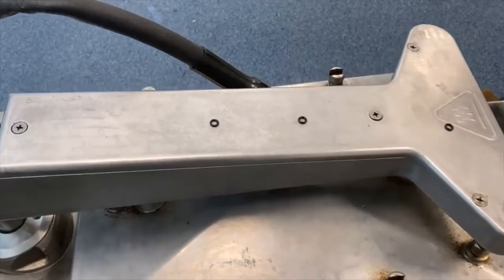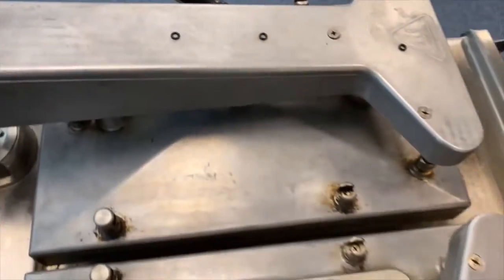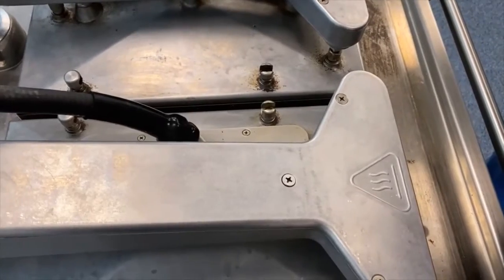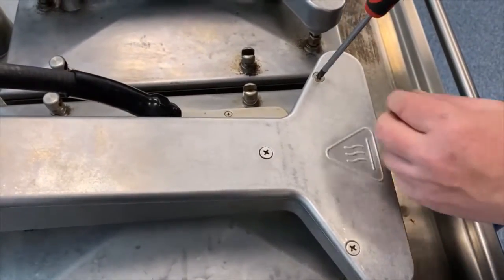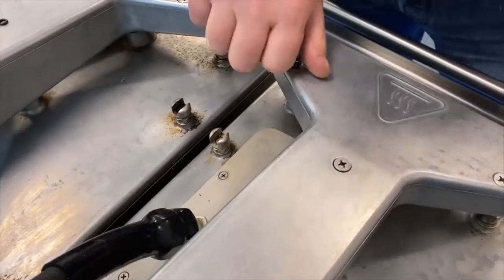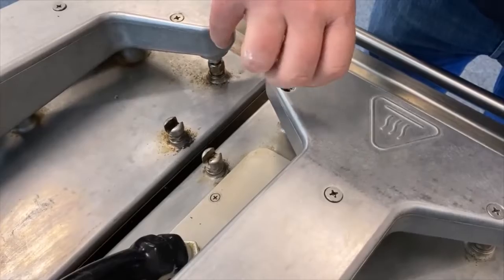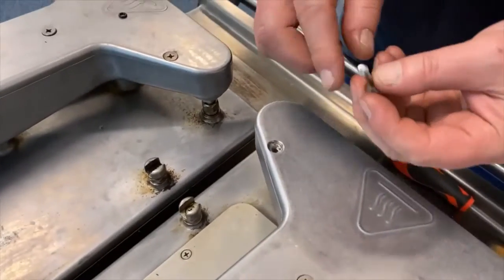In the new o-ring kit or PM kit you'll also see a number of small o-rings. These are to go over the captive screws in the arm. If we remove the arm screw — this is captive, so once you've undone it you'll have to lift it up and rotate it at the same time — it'll then unthread from the arm.